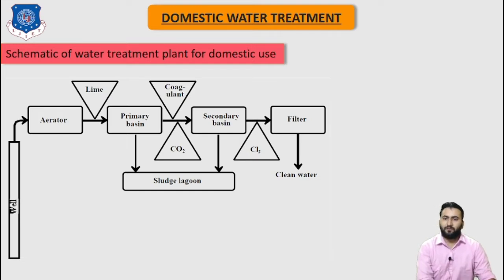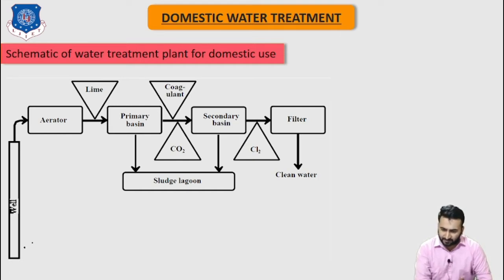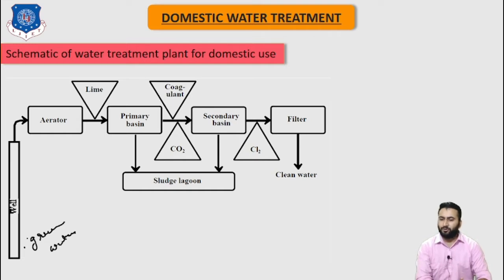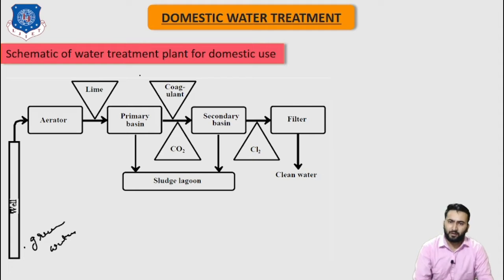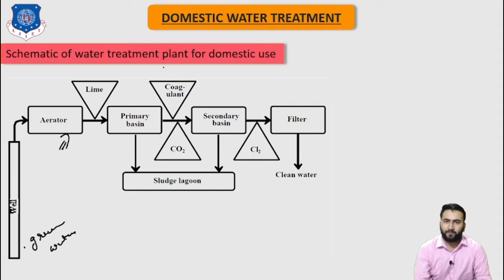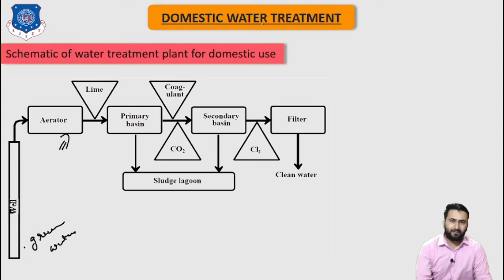This facility treats water containing excessive hardness and high levels of iron. The raw water is taken from the wells — that is, groundwater. The raw water taken from the wells first goes to the aerator, where contact of water with air removes volatile substances such as hydrogen sulfide, carbon dioxide, methane, and volatile odor substances.